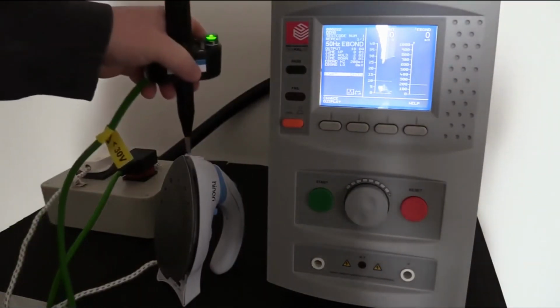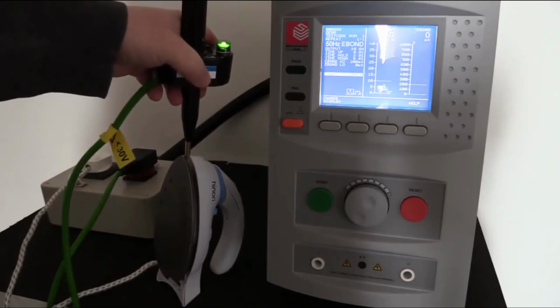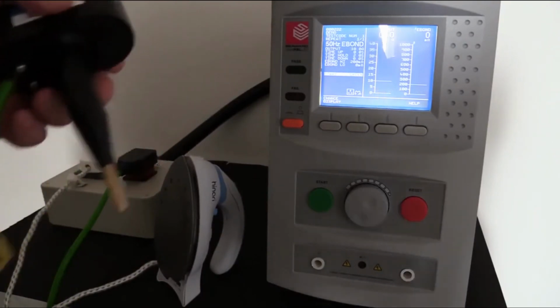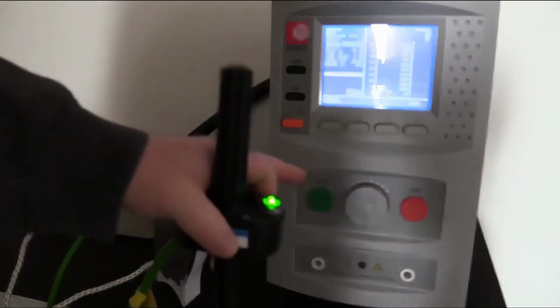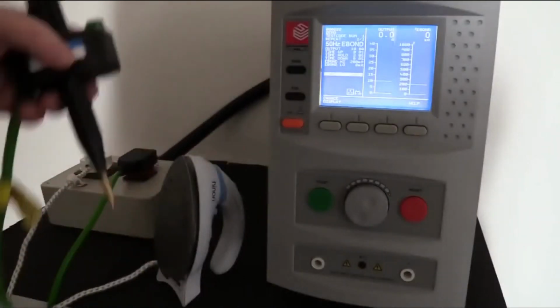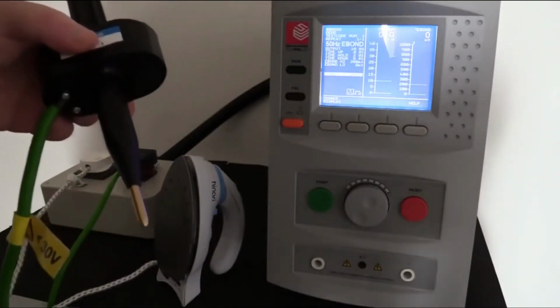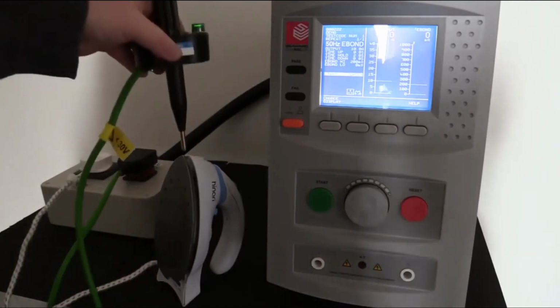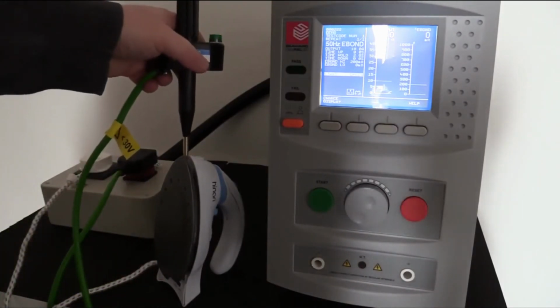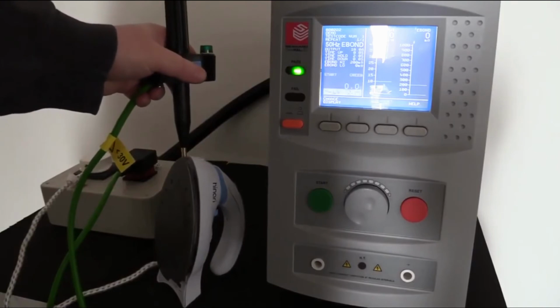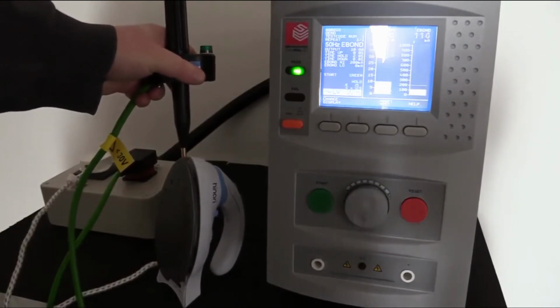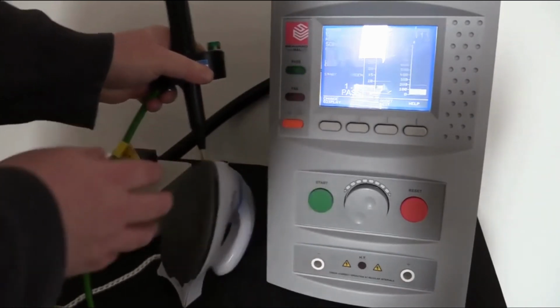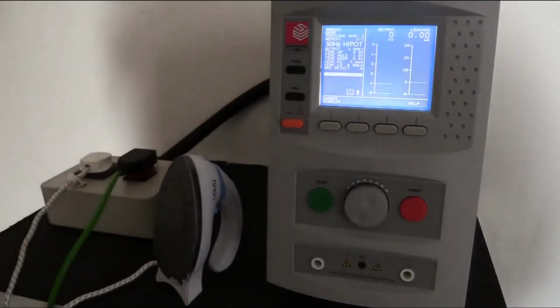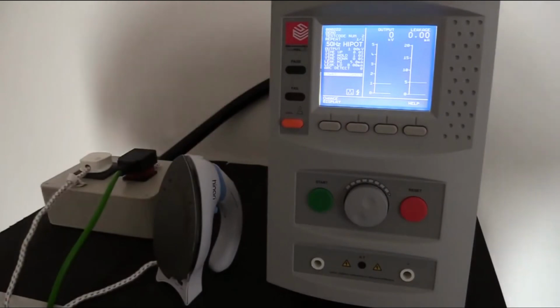So let's start the test away and see if it passes. Firstly, I need to go onto the metallic surface of the product. The probe also acts as the start button, so I don't necessarily need to press the green start button in order to test the product. Simply take the probe, make contact with the metallic surface, depress the probe, the test will begin. Providing everything is good, the test will pass. You can see the pass indication. We can then remove the probe and the HAL will move on to the next test.